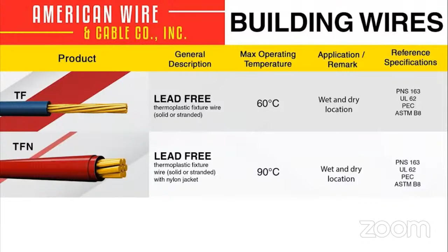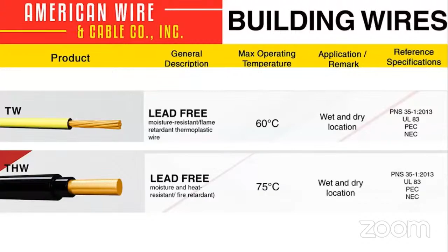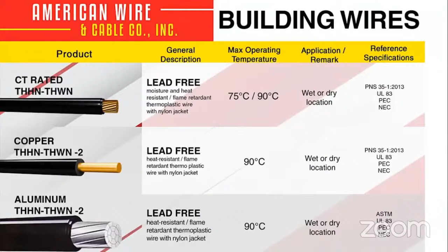TW wires, lead-free, moisture-resistant, flame-retardant thermoplastic wire, rated 60 degrees Celsius. THW wires, lead-free, moisture and heat-resistant, fire-retardant, rated 75 degrees Celsius. THHN, THWN wires, lead-free, moisture and heat-resistant, flame-retardant thermoplastic wire with nylon jacket, rated 75 degrees to 90 degrees Celsius. THHN, THWN-2, lead-free, heat-resistant, flame-retardant thermoplastic wire with nylon jacket, rated 90 degrees Celsius. Aluminum THHN, THWN-2, lead-free, heat-resistant, flame-retardant thermoplastic wire with nylon jacket, rated 90 degrees Celsius.